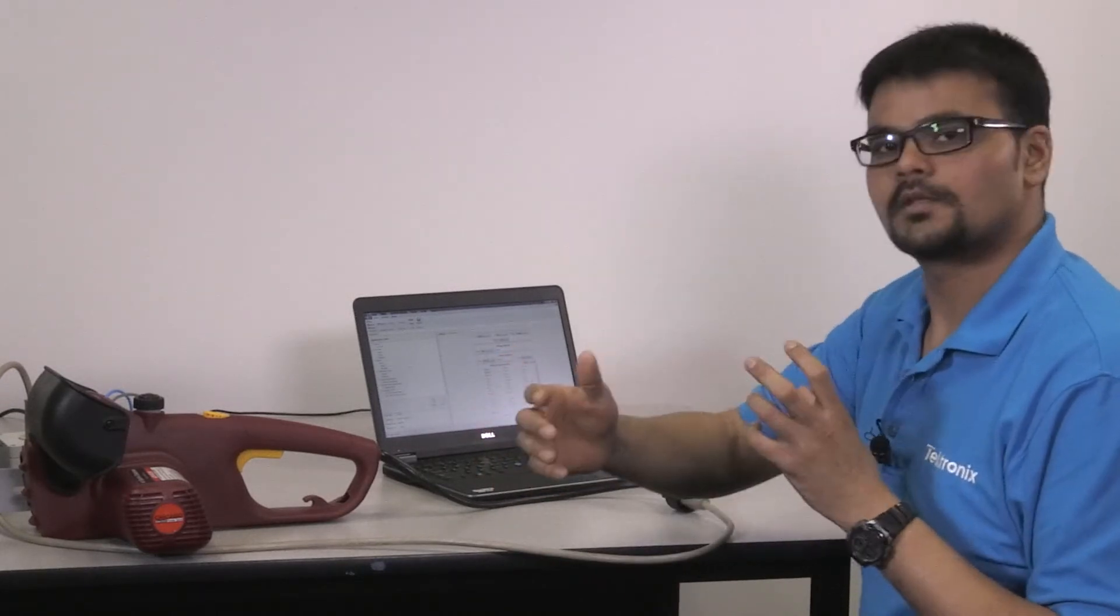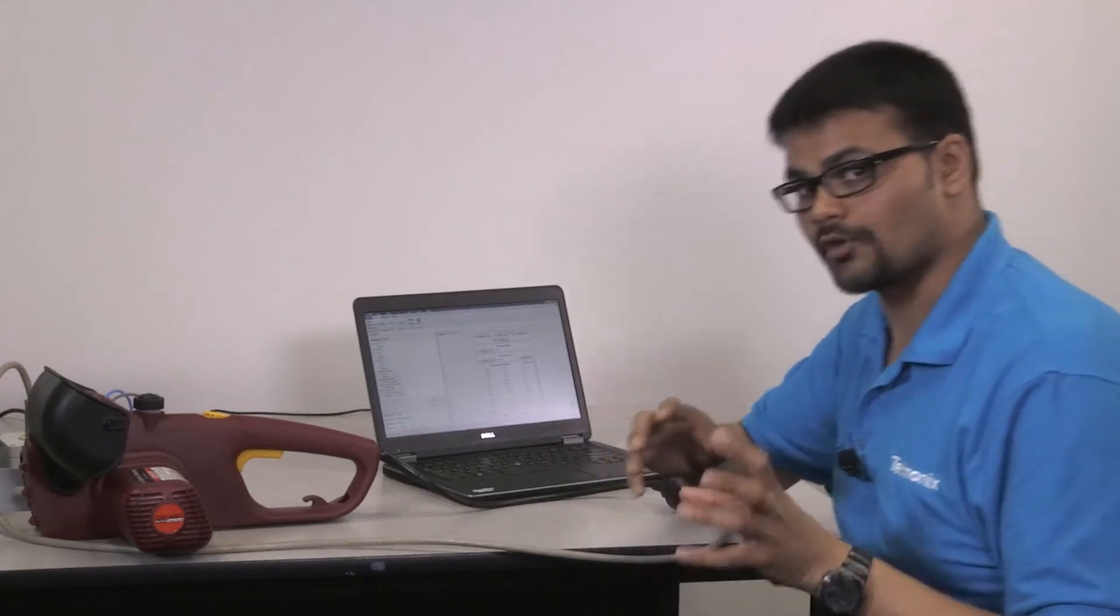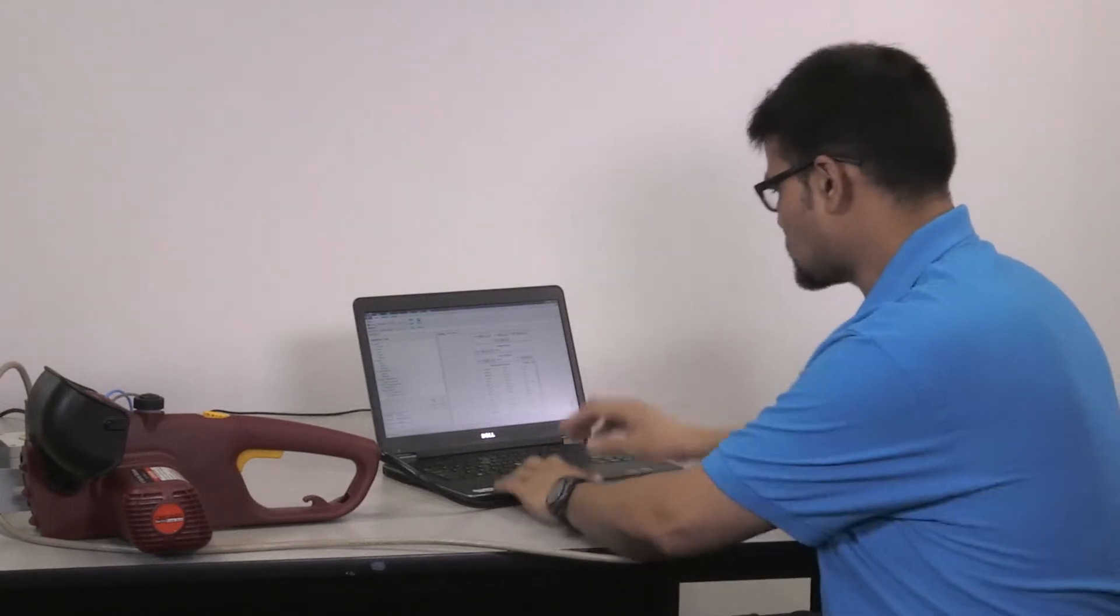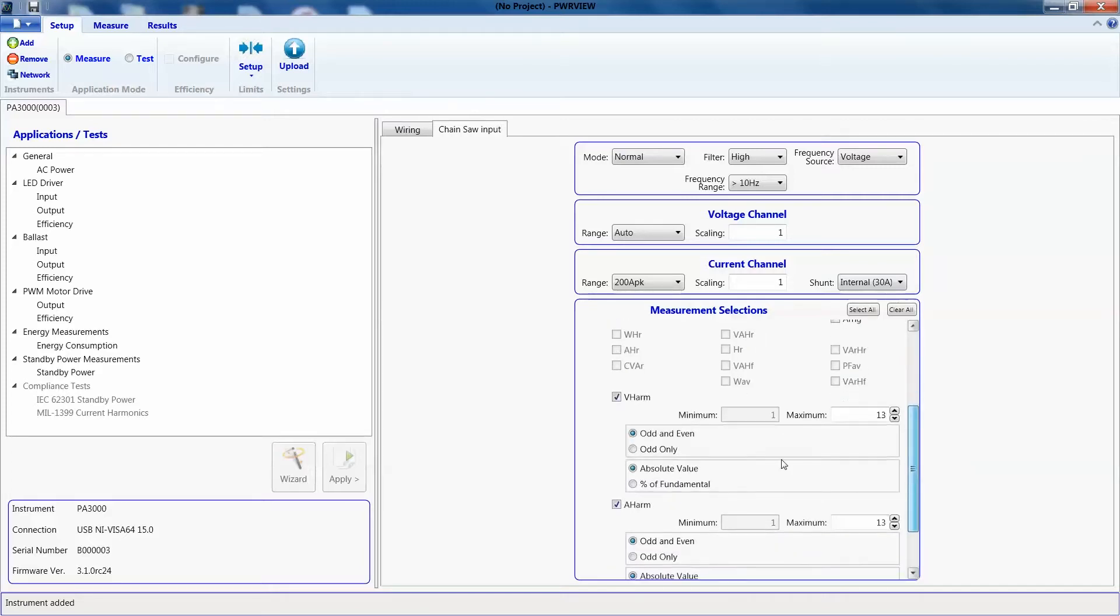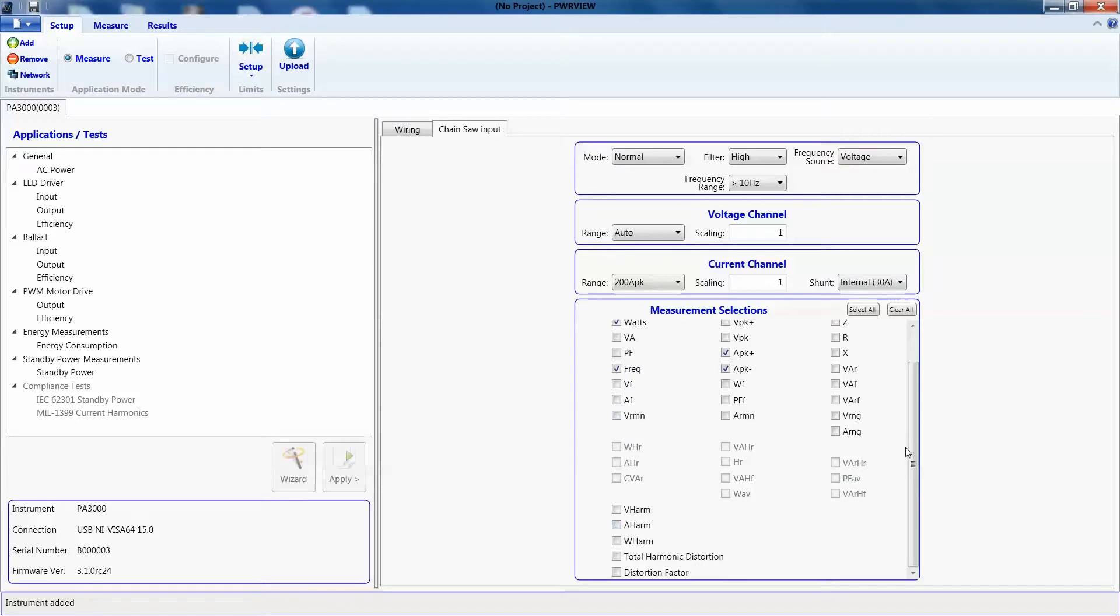So, you don't want PowerAnalyzer in auto-ranging while you're trying to measure inrush current. So, we are doing the maximum range here. We don't need the harmonics for now, so we'll just get rid of them and that should do it.